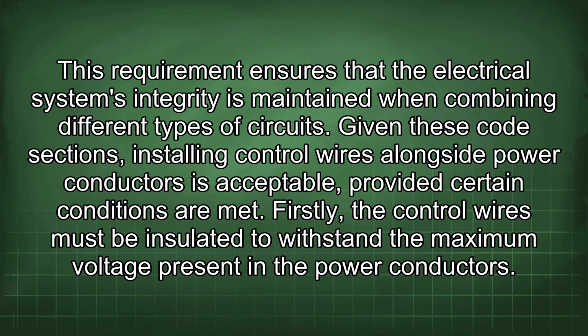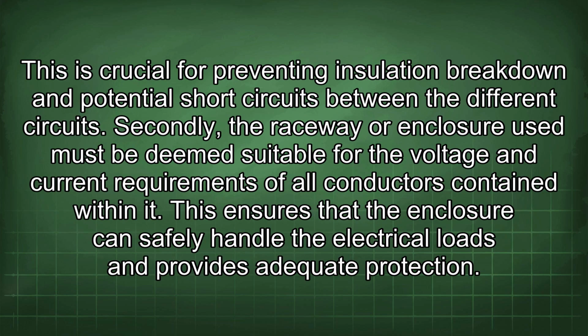Given these code sections, installing control wires alongside power conductors is acceptable, provided certain conditions are met. Firstly, the control wires must be insulated to withstand the maximum voltage present in the power conductors. This is crucial for preventing insulation breakdown and potential short circuits between the different circuits. Secondly, the raceway or enclosure used must be deemed suitable for the voltage and current requirements of all conductors contained within it. This ensures that the enclosure can safely handle the electrical loads and provides adequate protection.